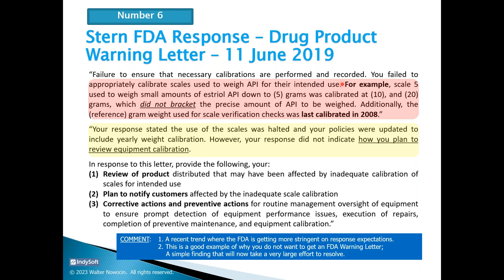Additionally, in this issue, the reference gram weight used for scale verification was last calibrated in 2008. If you take note of the date here and take note of the letter, that's more than 10 years that the reference gram was not calibrated. Those of us in calibration are aghast at that, of course, but that's the situation.